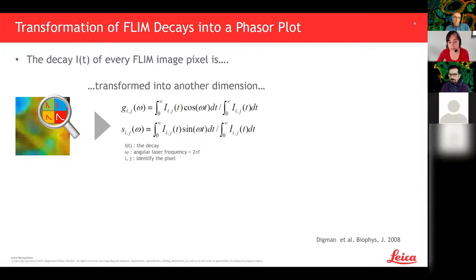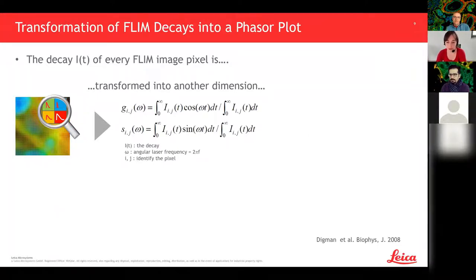Short lifetimes appear on the right because with a short lifetime the phase shift is only slight and modulation remains high — very similar to the excitation. For long lifetimes you get a large phase difference and lose modulation, so you move toward the origin of the phasor. In time-domain FLIM, such as FALCON with TCSPC, we have a decay curve for each pixel. To go from time domain to frequency domain you simply apply a Fourier transform.